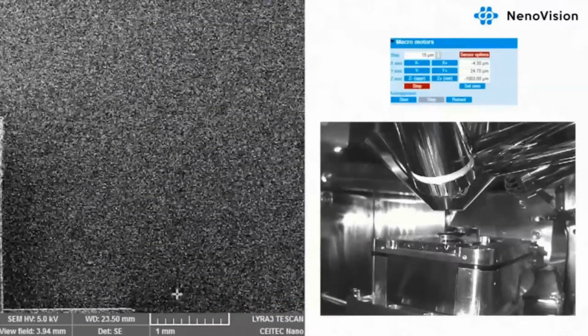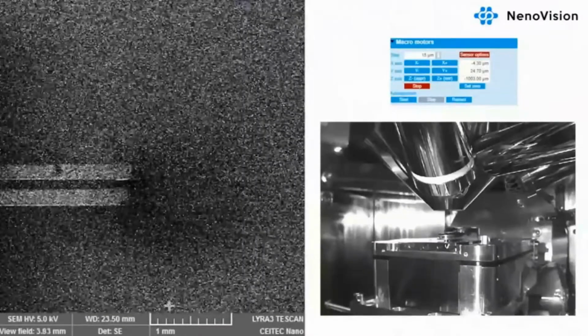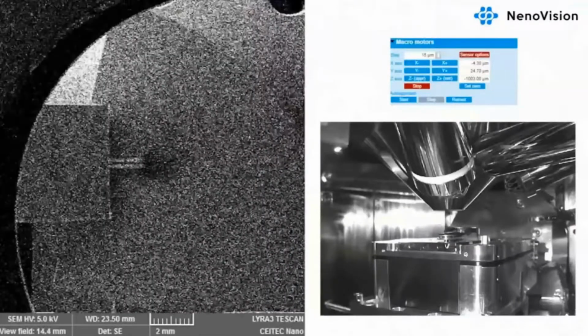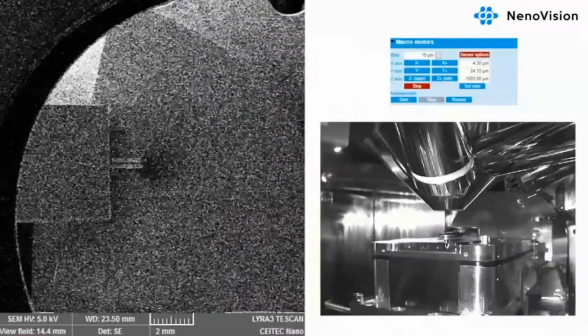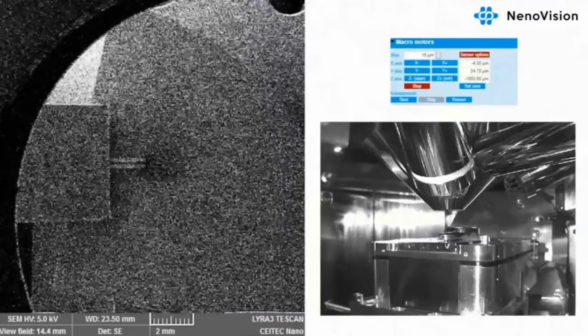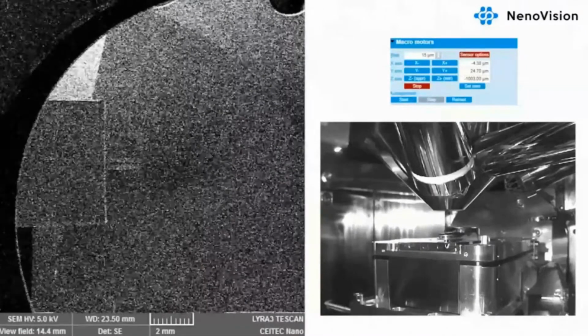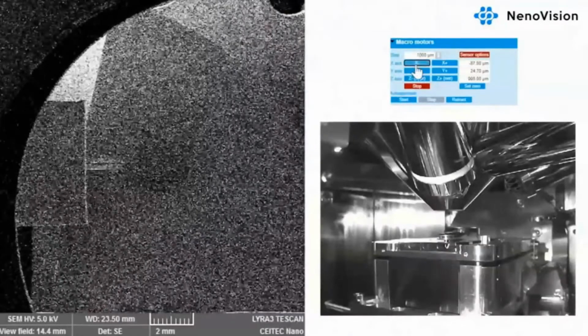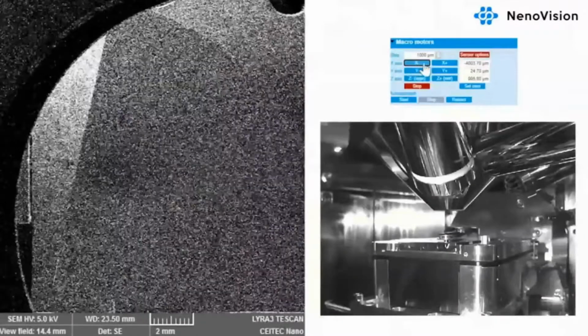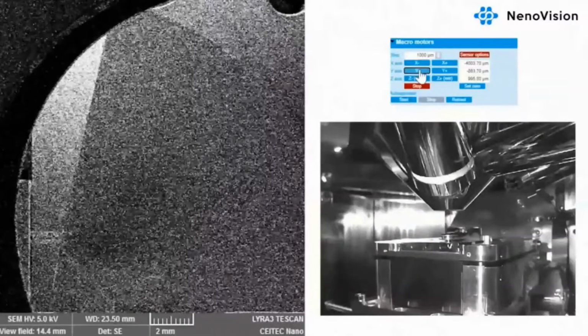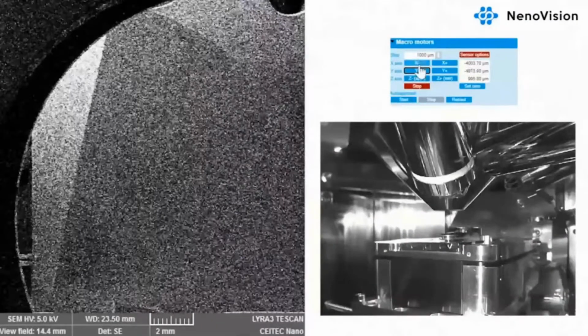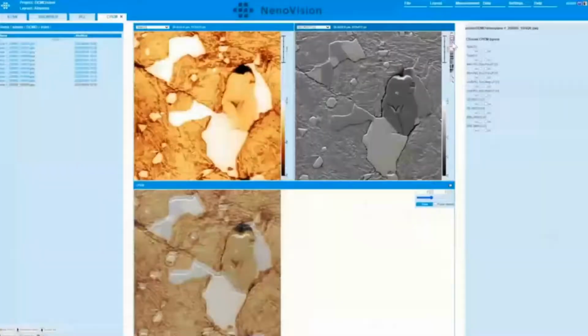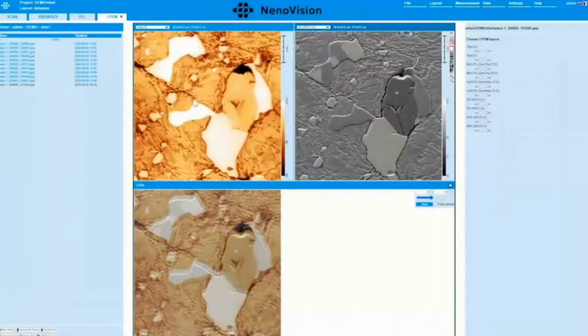The next procedure may be done before, during, or after venting the chamber. Pressing the buttons in the macromotor's box and choosing the step, we move the tip away from the sample. It is especially useful when changing the sample with no need of exchanging probe. The measurement is all done, so we remove the LiteScope the same way as we installed it before. We only need to remove the offset caused by placing the electron beam spot next to AFM tip.